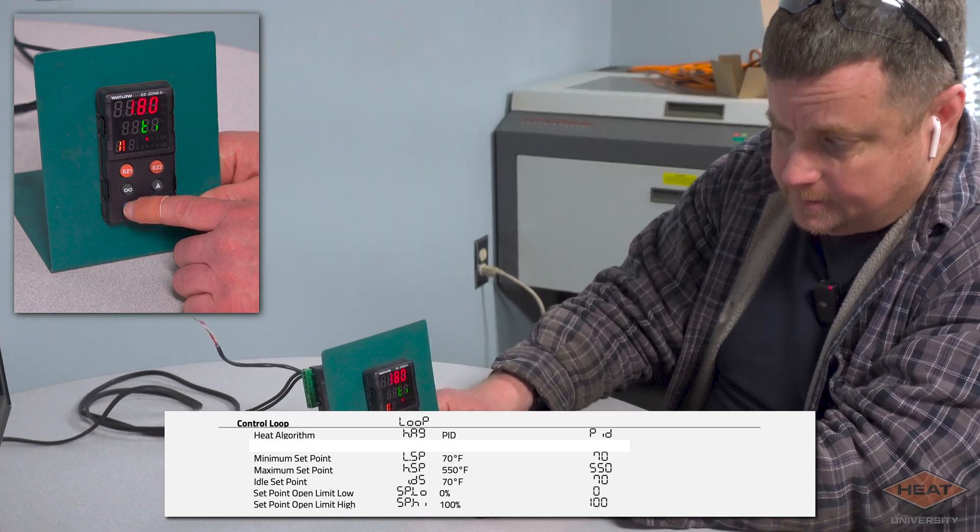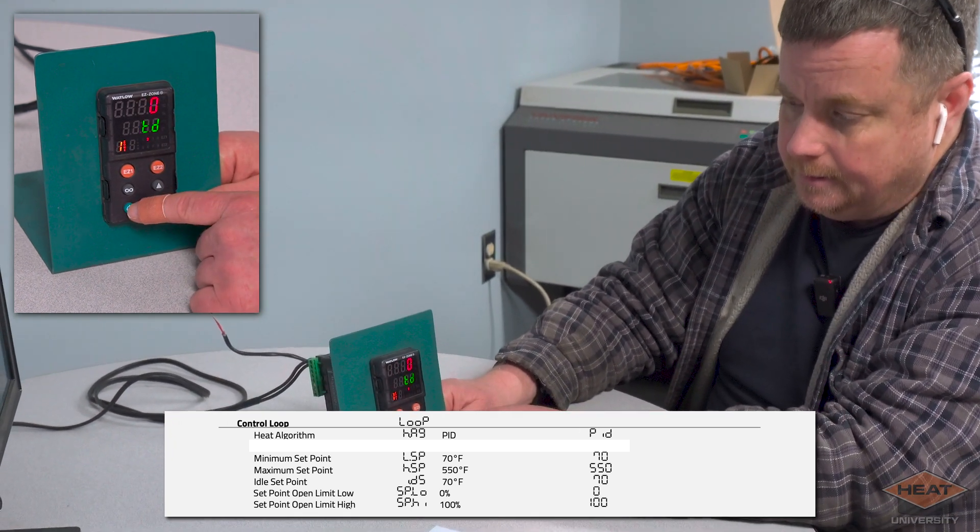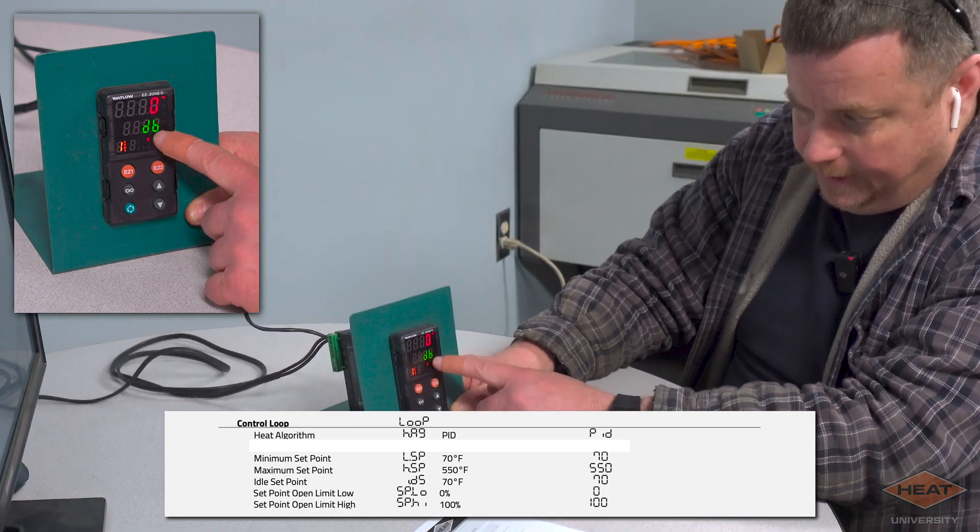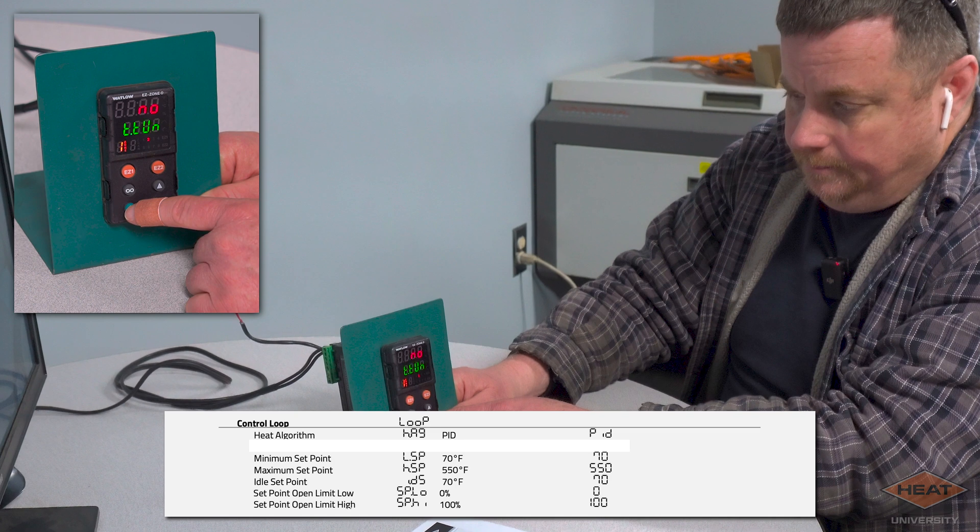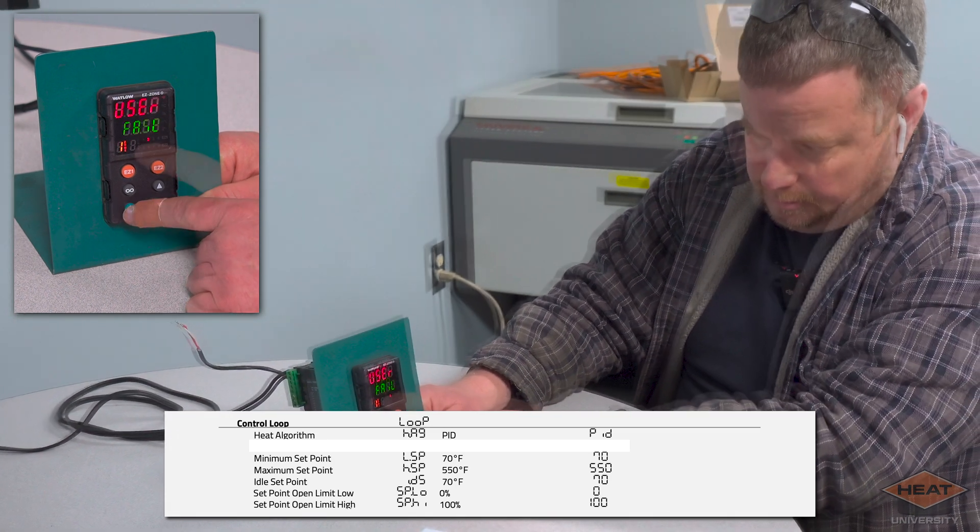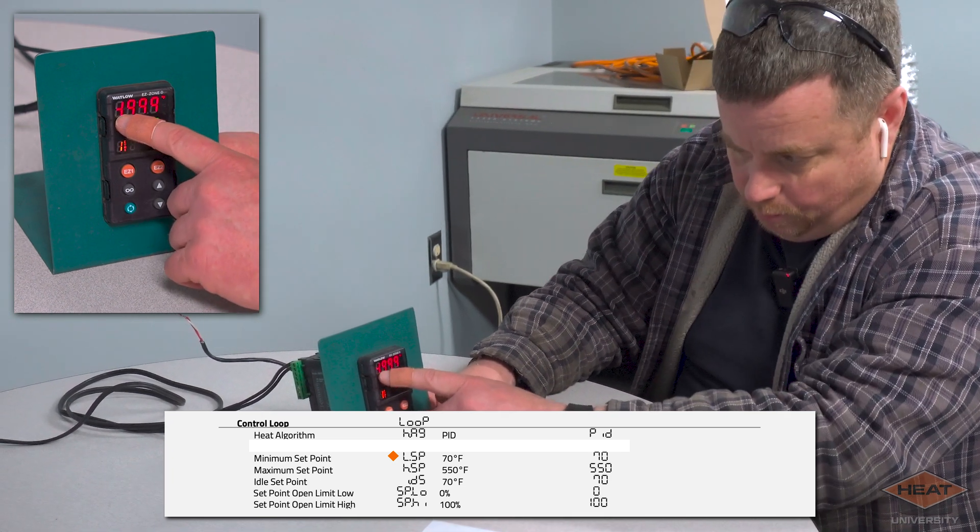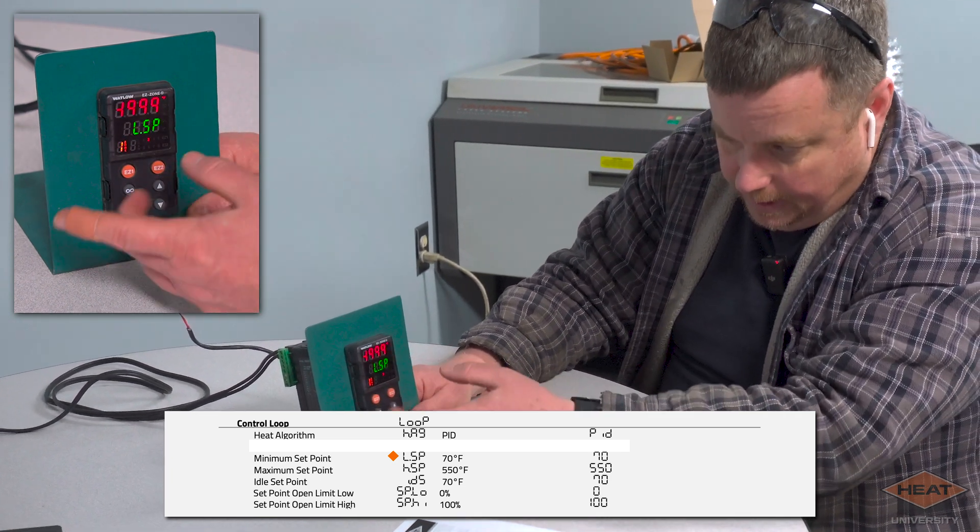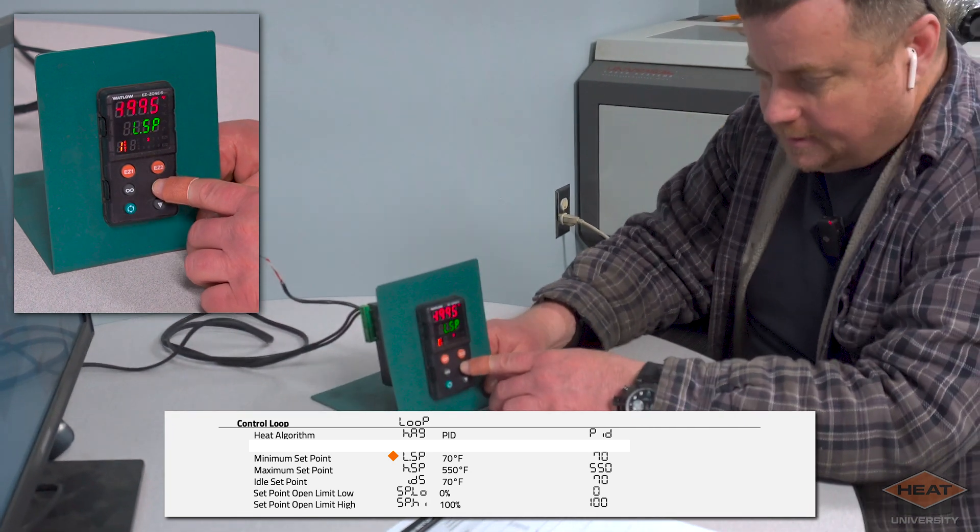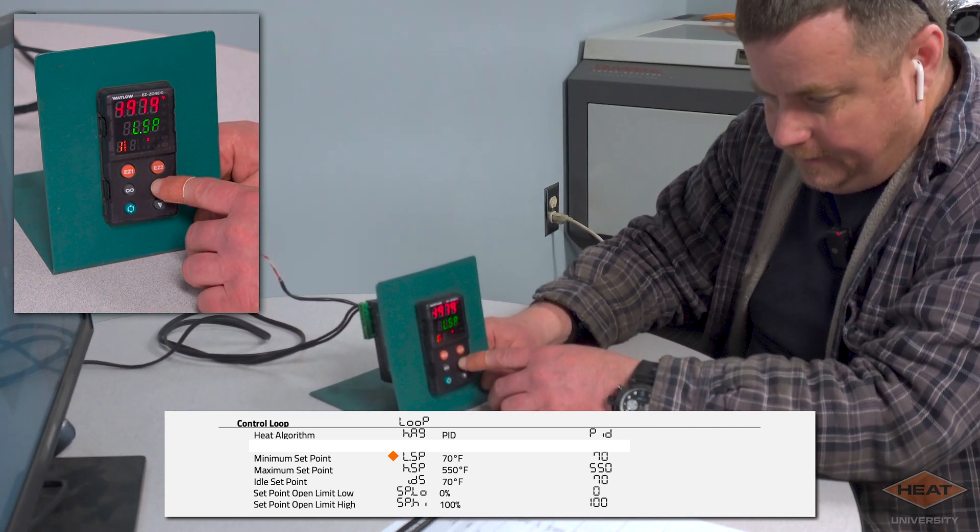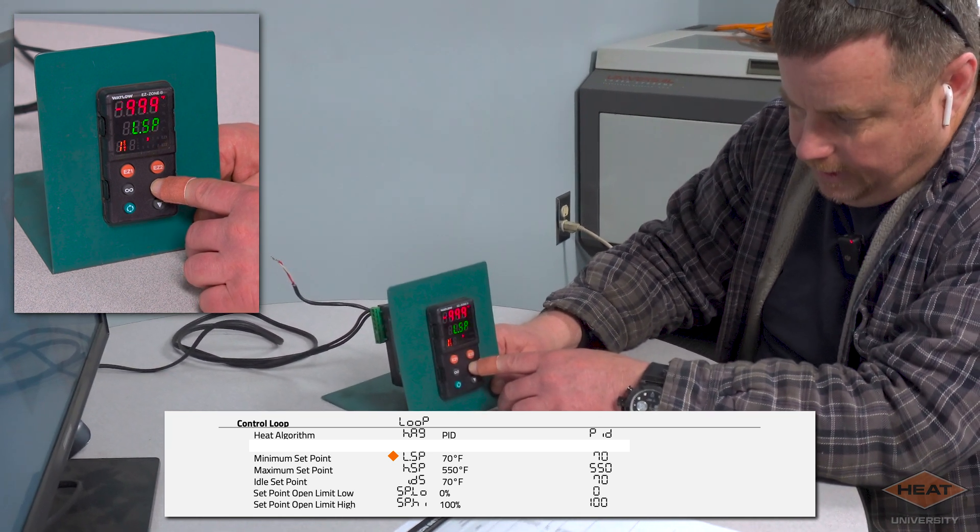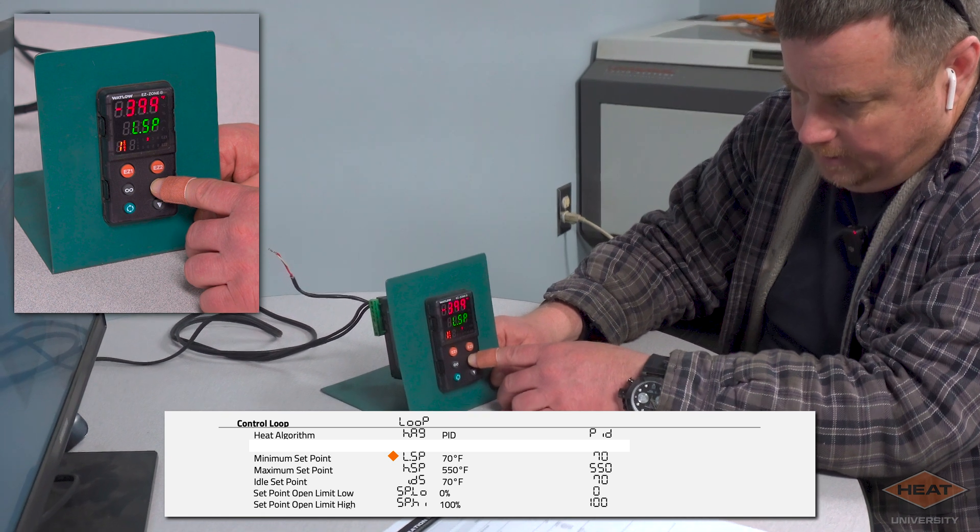Then we'll hit the cycle button again. The cooling algorithm is off because this setup does not have cooling. It's our heating proportioning band 25 degrees, our time integer 180, our time delay, but we're just going to keep hitting this. That's our dead band. We're just going to keep hitting this until we come to our low set point. Now our low set point from the factory is just going to come as minus 1999, and typically our systems' low is either 70 or 50. It's typically 70, so we're just going to hit the up arrow until we get to 70 degrees.